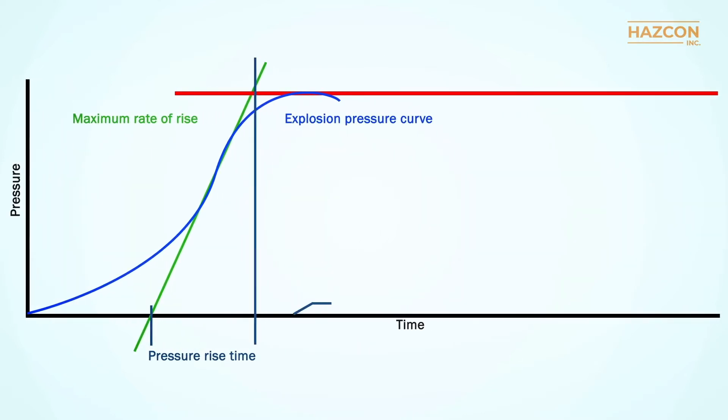Pressure piling changes the dynamic. The pressure curve becomes an irregularly shaped wave that illustrates the cascading effect of pressure piling, the multiple explosions that take place. Pressure piling involves, as the name implies, the buildup of pressure, which can be higher than the expected peak pressure. There is presumption of pressure piling when the pressure rise time is less than 5 milliseconds.